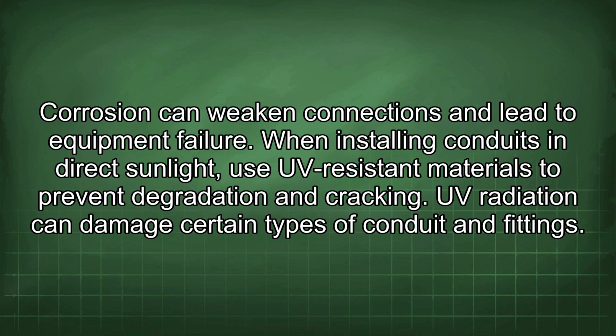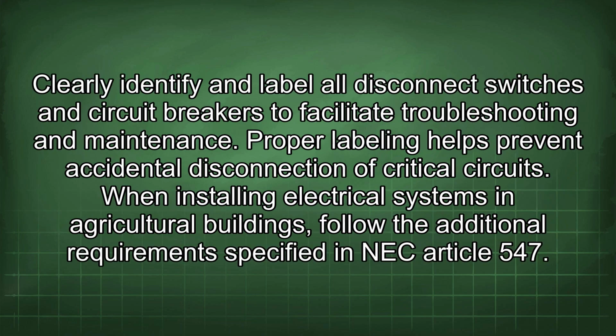When installing conduits in direct sunlight, use UV-resistant materials to prevent degradation and cracking. UV radiation can damage certain types of conduit and fittings. Clearly identify and label all disconnect switches and circuit breakers to facilitate troubleshooting and maintenance. Proper labeling helps prevent accidental disconnection of critical circuits.